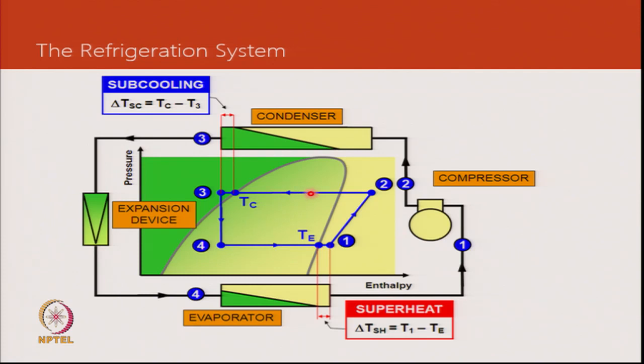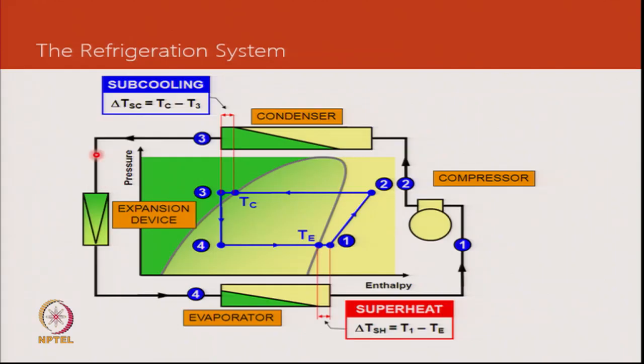If we know the condensing temperature, we know the condensing pressure at saturation conditions. Defining sub-cooling at 4 degrees with a condensing temperature of 55°C gives a refrigerant temperature of 51°C. Assuming no pressure drops in the liquid line or evaporator, the expansion device inlet pressure corresponds to 55°C condensing. With an assumed evaporating temperature of 7.7°C, for R22 the suction pressure would be 77 psi gauge and the high side 300 psi gauge.